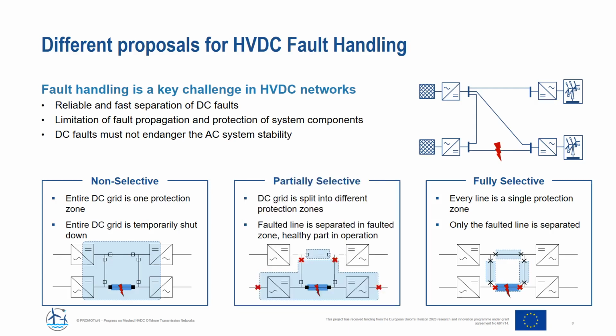The third option is the partially selective option, where the DC grid is split into different protection zones, and each of these zones can have different protection strategies, for example, non-selective or fully selective. The separation is done by DC circuit breakers as the protection zone interface.